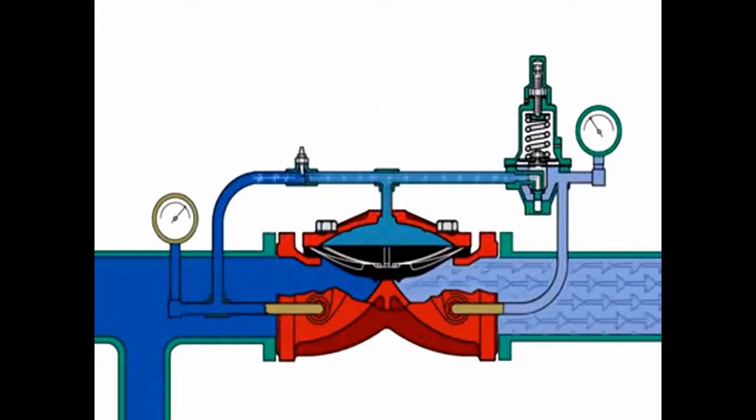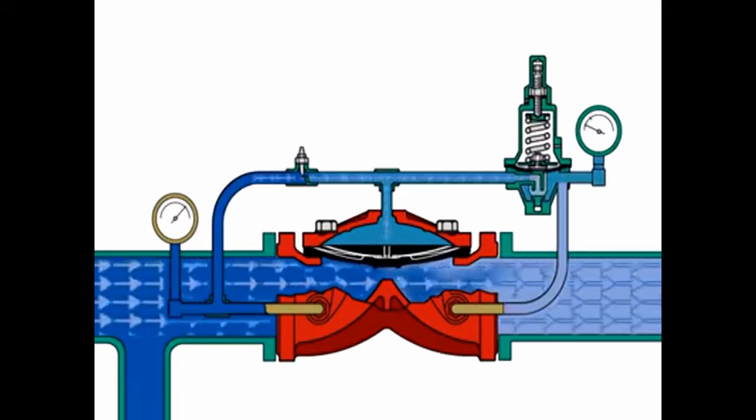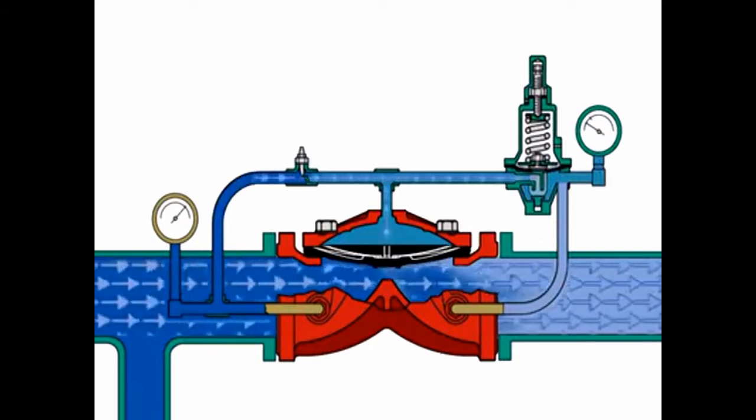When there is a flow demand downstream, outlet pressure drops below the set pressure. The pilot valve seat opens to relieve pressure from the diaphragm chamber, allowing the PRV1 diaphragm to lift, opening the valve.